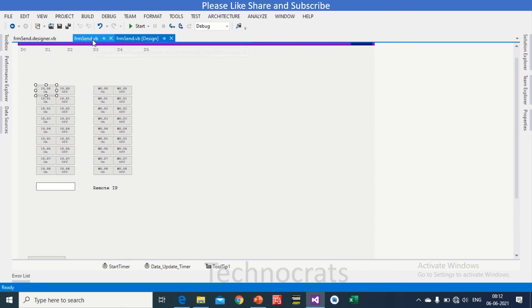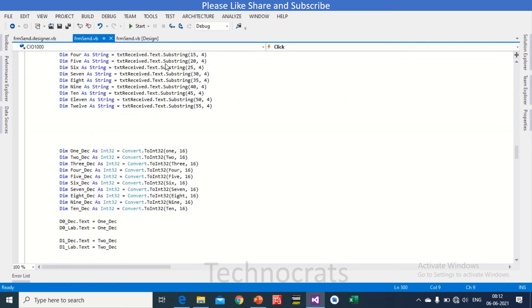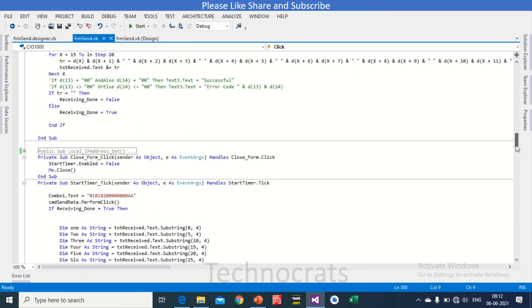Now I want to read the data memory area, as I mentioned here D0, D2 to D5. Okay, so what I will do is I will just create another command that is 0101. Now 82 is the code, so 0101 is for, 0101 is for read, 0102 is for write.